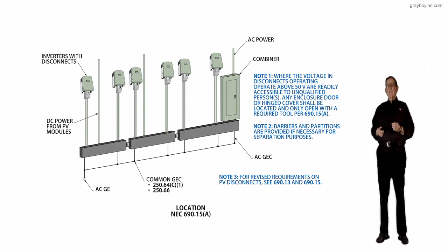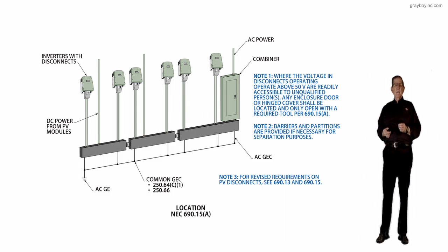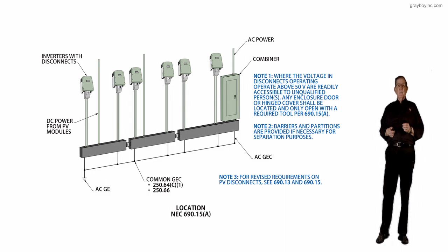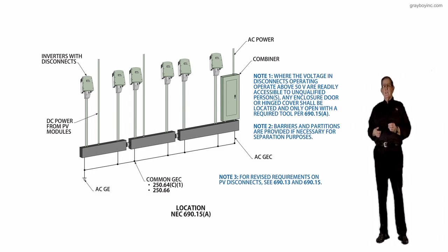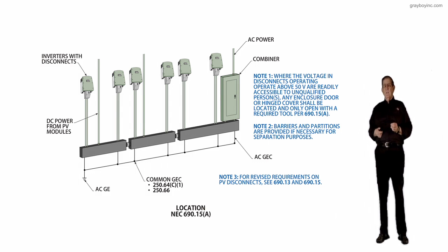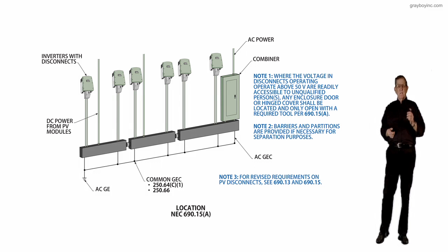The installation of PV systems has created an opportunity for placement of disconnect switches in locations that are accessible to other than qualified personnel. The disconnect enclosures can often be easily opened, exposing potential life-threatening voltage and current levels if contacted by personnel. The disconnect equipment is being installed on accessible external and internal surfaces of buildings, in garages, and in almost any room except the bathroom in dwellings.